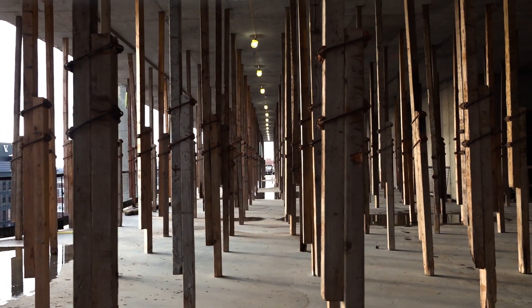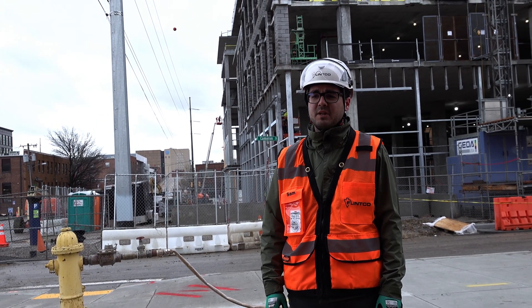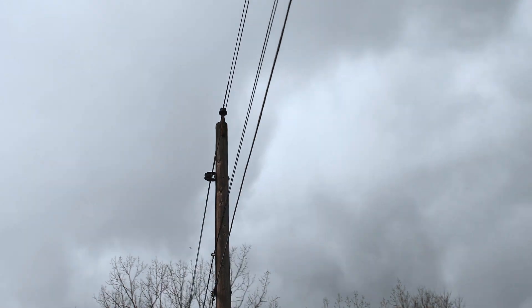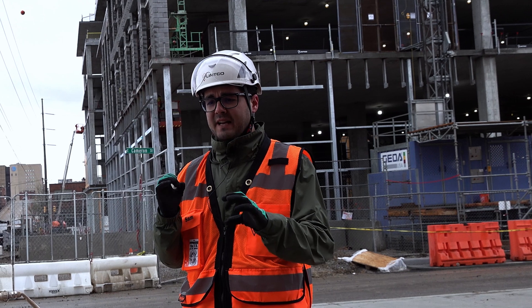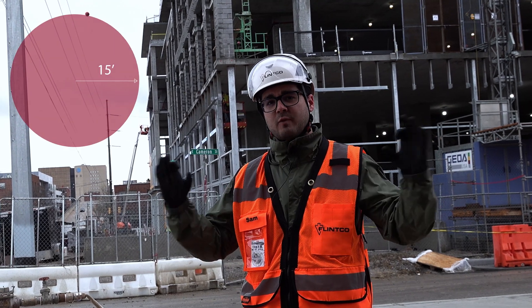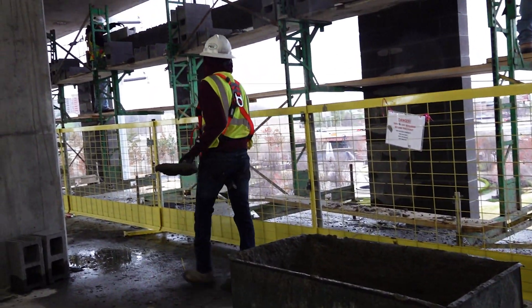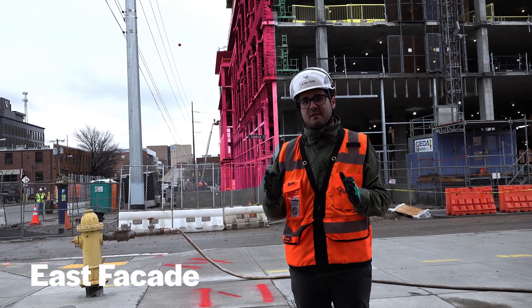From the very beginning of this project, both our owner and our project team at Flintco had some concern about the high voltage power lines you see here behind me on the east side of the project border. OSHA dictates that a construction worker cannot safely come in contact with those power lines, and also that they must maintain a 15-foot safety radius around those high voltage power lines. We did not believe we could actually construct masonry on this east facade safely outside of that OSHA boundary.